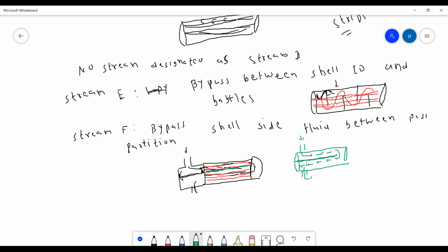But if there is a gap between this tube sheet, for example, this is the tube sheet, and this partition plate, this is the partition plate, then what will happen is the shell side fluid will directly bypass between the gap between this tube sheet and the pass partition plate.